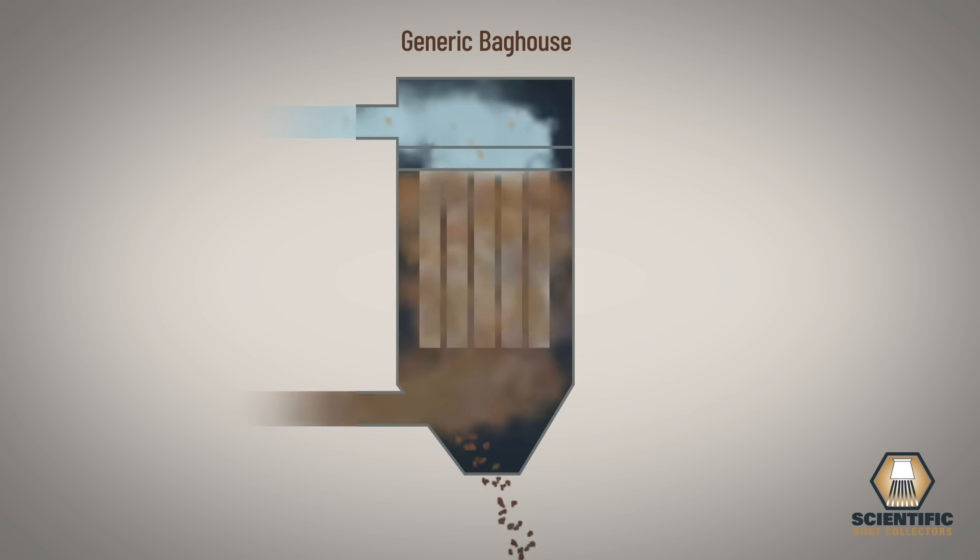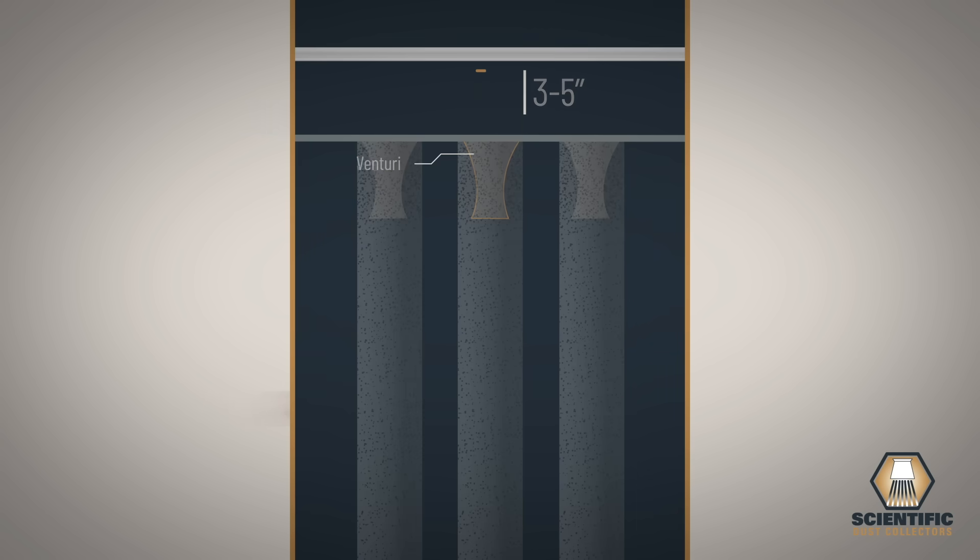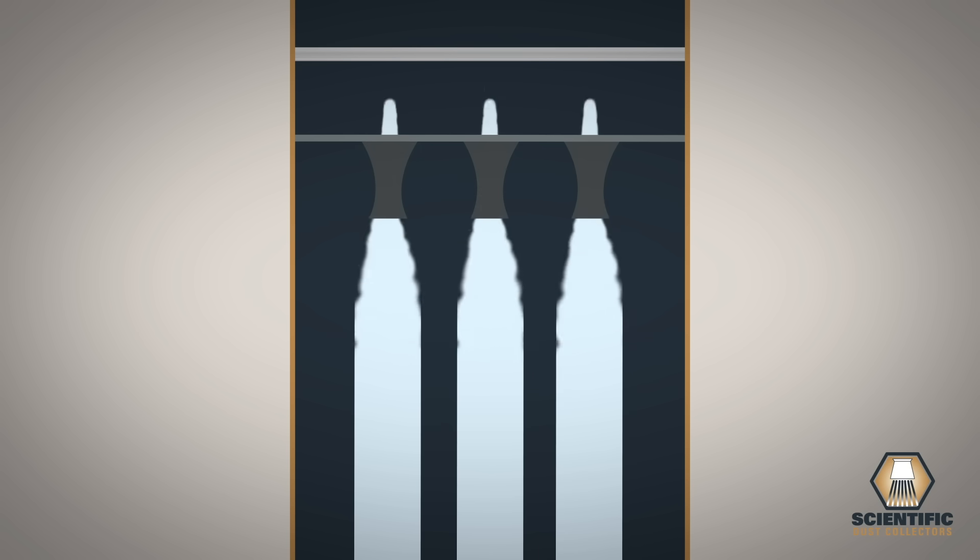The dirty air then passes through the filter media and is exhausted as clean air through the clean air plenum. An orifice located 3 to 5 inches above the Venturi expels a high pressure, high velocity jet of air.